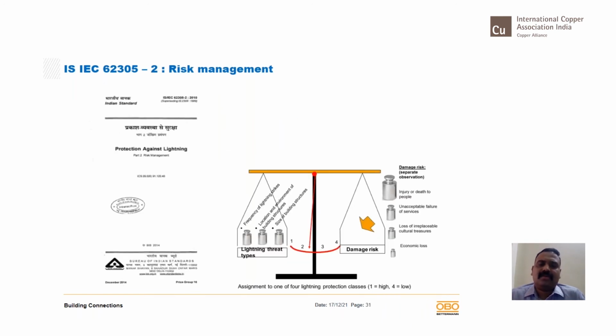Part 2 talks about risk assessment. Now, this is a very critical part for designing a lightning protection system. I told you, even in the old type of theaters, you may see one Trishul kind of rod at one corner and they claim everything is protected. And statutory approvals were also given just on the basis of the one rod available. Now, this will not take care of the complete structure because there may be chances that the side flash may hit, or the other end of the building may get hit because of lightning.